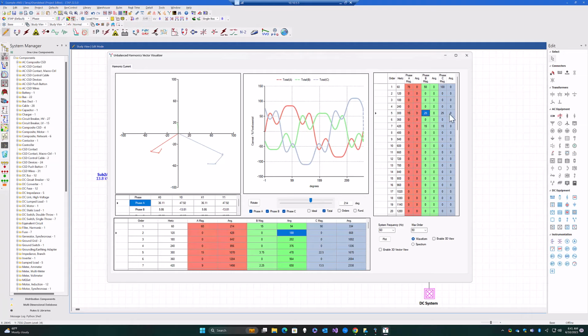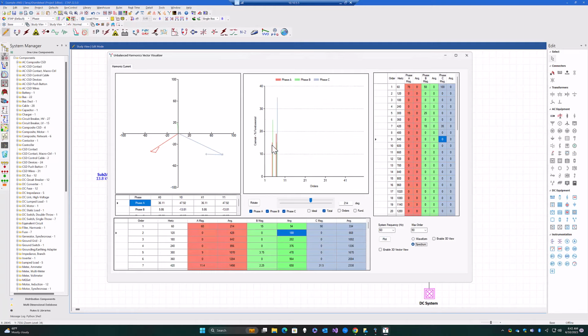We can change this to something even more substantial, more exaggerated, if you may, just so that you can investigate what happens not only when the fundamental power supply is unbalanced, but what happens if you have a tremendous amount of unbalance even in the harmonics themselves. As you do so, you can see that the magnitude of the waveform, including its distortion, increases substantially. We went from nearly 15 to 20% distortion to almost 35% distortion by having unbalance in our harmonics.